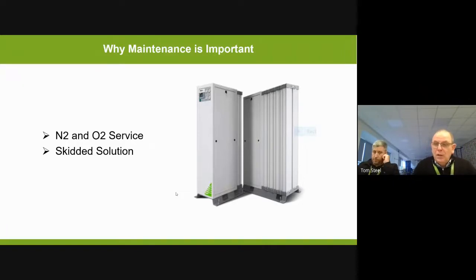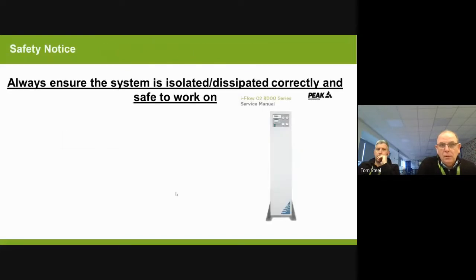Filters will get clogged, especially if you're putting 4,000 litres a minute through them. They will eventually get clogged. They will cause pressure drops. Then we will see problems at either the delivery or the purity of the oxygen out to the user end. So again, just reiterating what I said, please make sure everything is isolated before you start any work on this system.